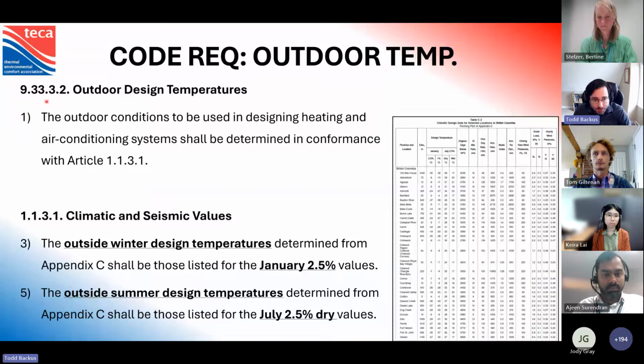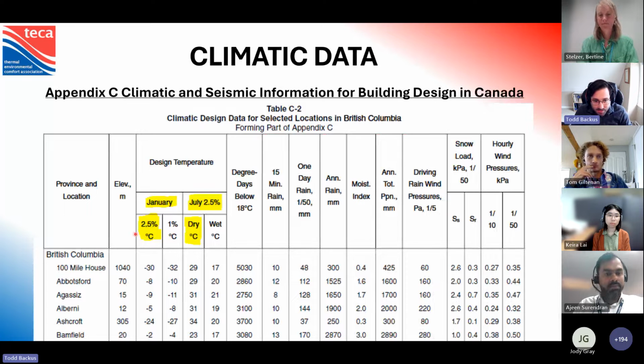So the outdoor design temperatures, those come from the BCBC. If you go into the appendix in table C, basically what we're looking at here is the outside winter design temperature shall be determined from appendix C, and they're the listed January 2.5% values. The outside summer design temperatures are the July 2.5 dry bulb values. So if you look, I have this blown up a little bit. So this is our winter temperature, and let's say we're in Abbotsford, so you're looking at -8. Our summer temperature, which is the dry bulb, coming over to Abbotsford, we're at 29 degrees C.